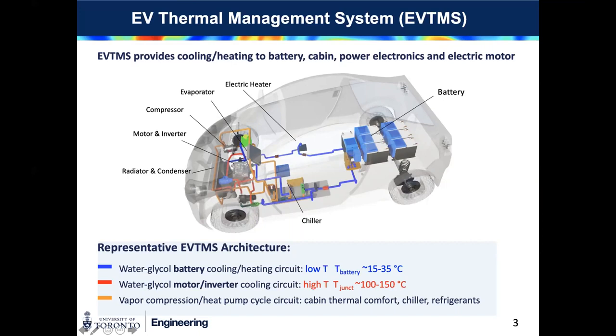The blue circuit performs the critical cooling and heating of the battery and keeps the cell temperature in the narrow range for optimal operation. This is the low temperature circuit, typically using water glycol cooling, where temperatures are significantly lower than in conventional internal combustion engine vehicles, with corresponding heat transfer challenges. Heating may also require preconditioning in cold weather, and we'll hear more about this from Stefan Elbel's presentation.